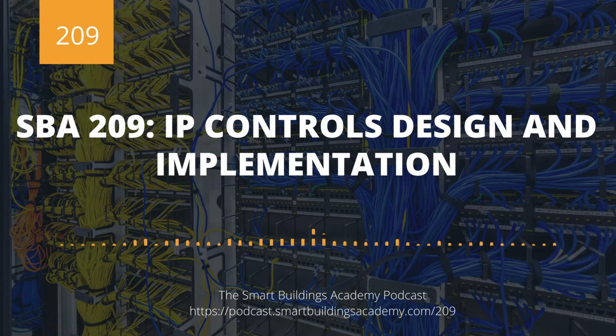At each controller, because we are using a network interface card, we have a MAC address. And that MAC address is the physical address of that network interface card. Now, at the network switch in which the physical field controller connects via typically Ethernet cable, that MAC address is associated with a port in an address resolution protocol table called an ARP table, and that ARP table is paired up with an IP address.